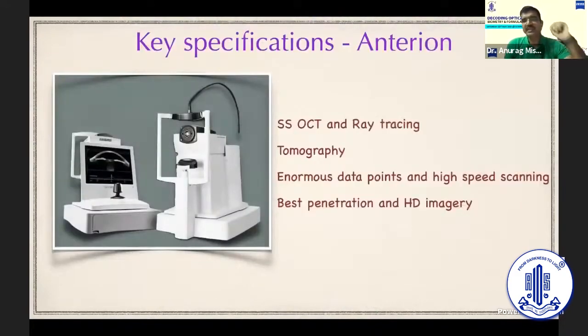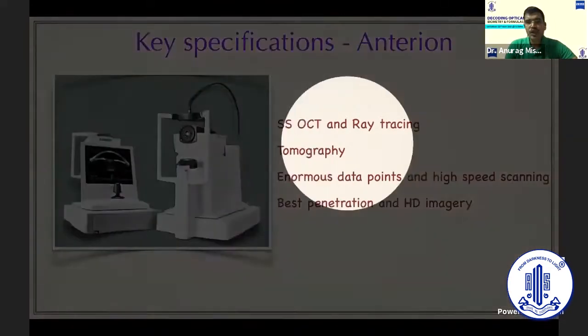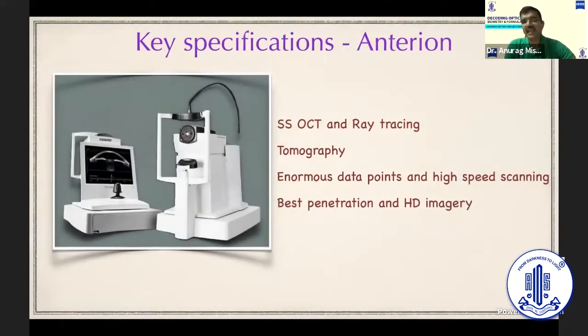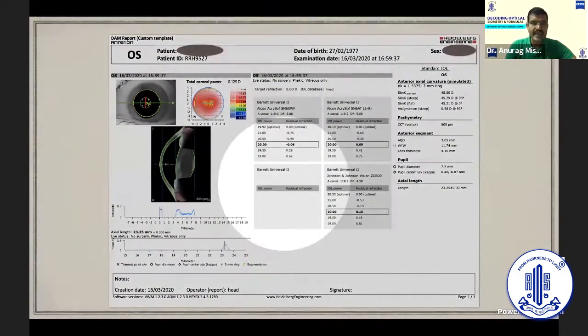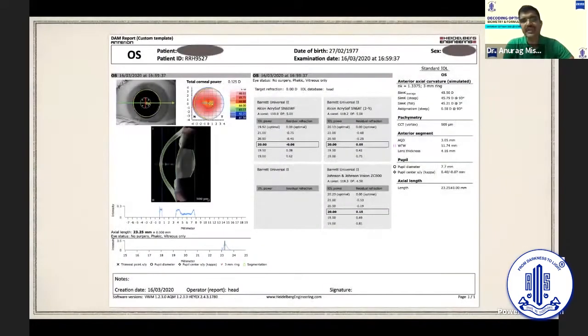The other SS-OCT based machine that I use is coming from the group of Heidelberg Engineering. It's called Anterion. It's got two technologies apart from SS-OCT. It also has ray tracing; it has tomography. It has enormous data points. It takes 16,000 data points just to give us the keratometry. It has an exceedingly good anterior segment OCT as well, as well as angle metrics. Excellent machine to work with. This is the printout that comes from the machine. It also gives us an A-scan in a divided setting, one the anterior, the other the posterior. There is a spike from which the machine has supposedly taken the reading from. It has different quality checks as well, as you will see a little while later. Fantastic machine to work with.